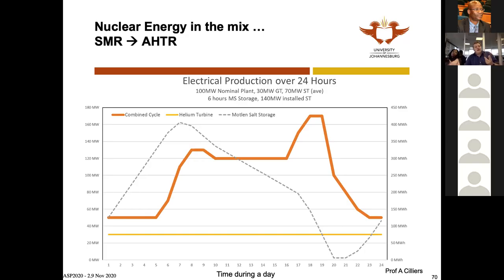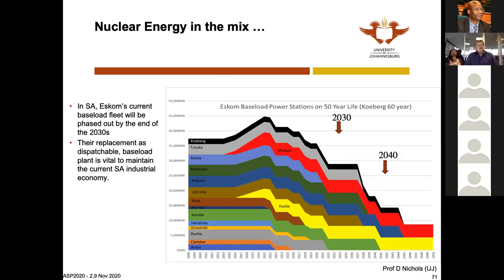One more crucial point: walk-away safety. There is no active safety feature in this reactor — zero. Any accident makes the temperature higher; as temperature increases, the Doppler motion of the uranium in the fuel broadens the resonances for neutron absorption and gobbles up the neutrons. The reactor always shuts down if it gets too hot. It cannot get too hot. It's all refractory materials, and because it shuts down when too hot, it passively cools. No active safety system is required.